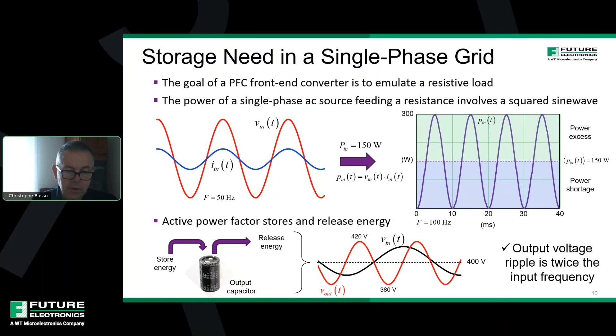Having more or less power at some point in time results in a voltage ripple appearing on the output, at twice the frequency of the input source, like 100 hertz in a 50 hertz environment. For stability reasons, you will set the control loop crossover frequency of the active PFC sufficiently low to exclude the ripple components from the regulation path. Otherwise, the loop will react on its own ripple and deteriorate regulation.